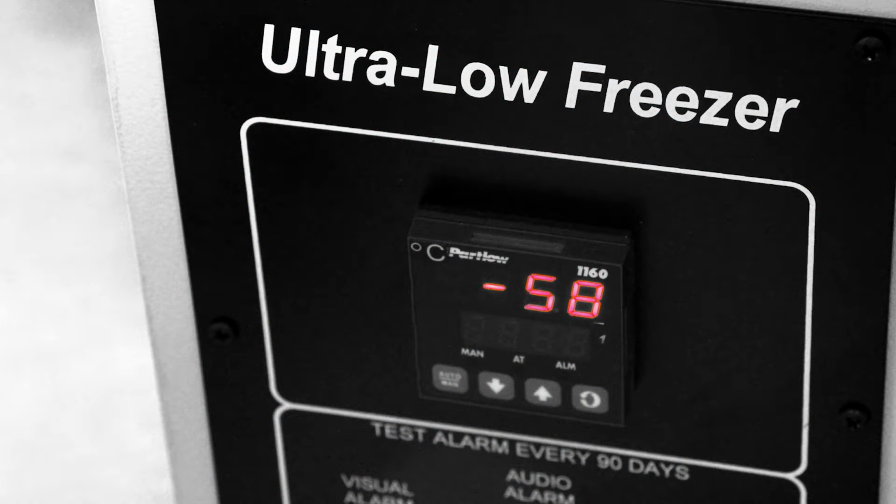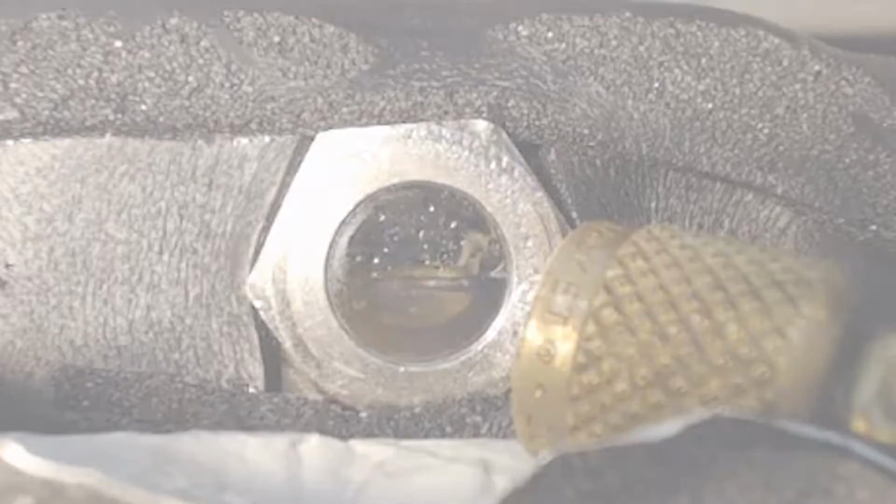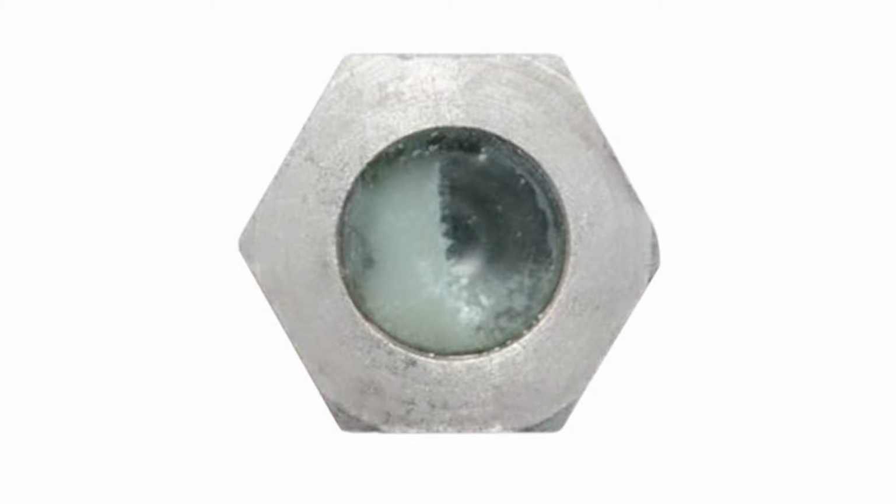The warm-ups result in service calls where the technician turns the unit off and then the frozen oil thaws. When the unit is restarted, it seems to be working properly until the oil clumps and freezes again, and then the whole cycle repeats itself.